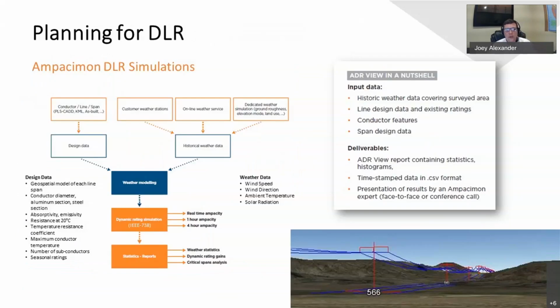So we do a pretty aggressive planning stage for our dynamic line rating deployments. That planning stage starts with the customer identifying the line they're targeting to have dynamic line rating on. We take in geospatial data, and also materials and thermal data on the conductor of that line, and we build a geospatial model of the line in 3 dimensions.